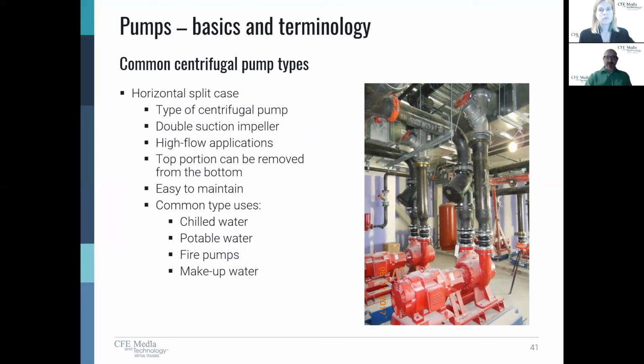In the case of a horizontal case that's split, this is a serviceable motor. We can take it apart physically. That's part of the design. But that means we have to have adequate space around that to work. Now, what you'll see in this photo is we have walking space. We can actually get to this pump, but one of the things you don't see is a disconnect or a VFD. Clearly, we have to control this, and I can tell you personally, I put a VFD on this motor. But where is it? Well, it can't be anywhere near this pump because it has serviceable components. And mechanical engineers need to tell their electrical engineer counterparts where they can and can't put their components.